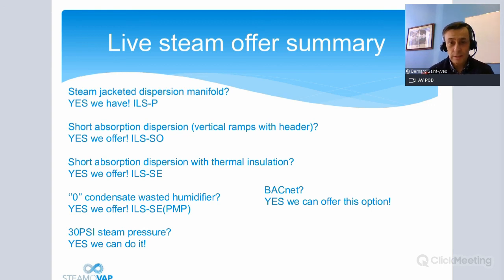Zero condensate wasted. Yes, we have an option. And 30 psi steam pressure. Yes, we can do it. Okay. The thing is, after the valve, the pressure is dropping to atmospheric. So you can have higher pressure before the valve. Of course, we have to be careful on the components we are selecting, but right after the valve and inside the duct, you will have no pressure or very limited pressure on the steam.